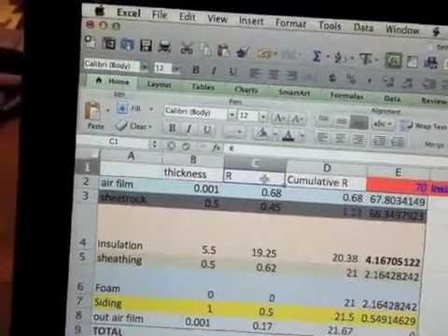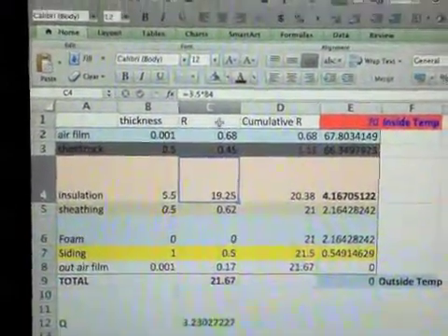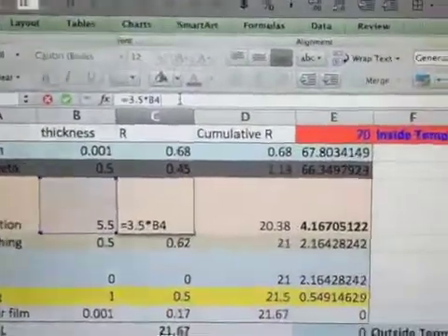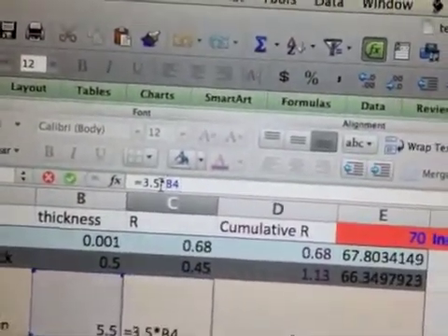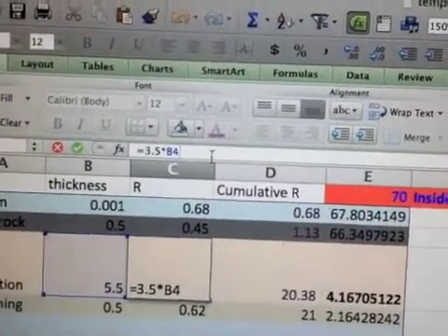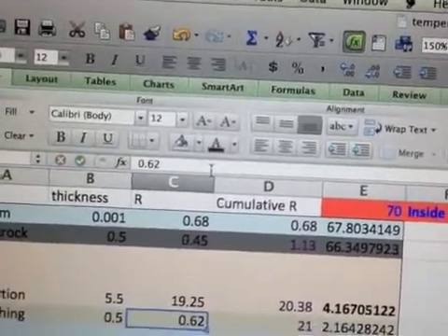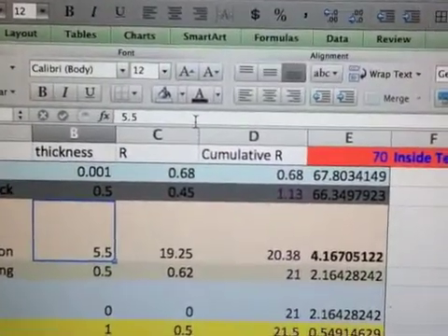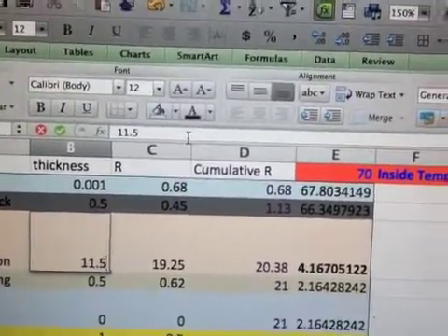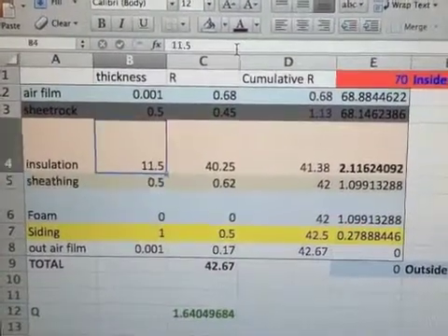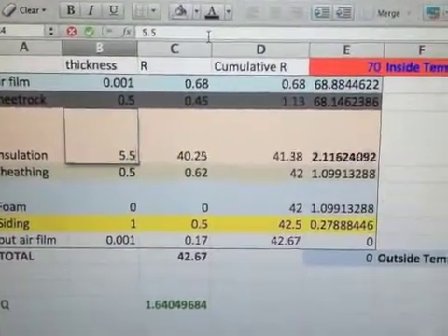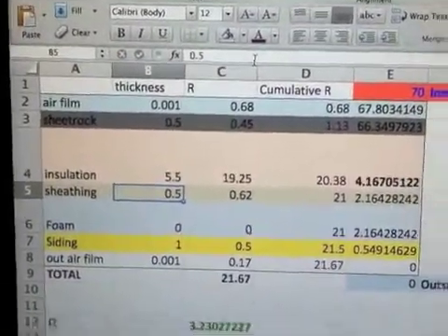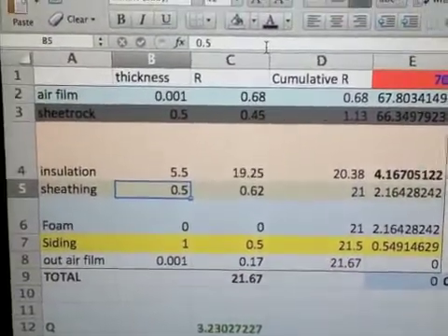Then I have an R value for each of these. Some of these are just given R values, and some of them are calculated. So if you look up in the formula bar, you'll see that I'm using an R value per inch for the insulation material, and then multiplying that by the number of inches of that material. So, for instance, if we decided we wanted a really thick wall, and we said we were going to have 11.5 inches of insulation, then we'd have an R40. But we're going to stick with the standard 2 by 6 framing.